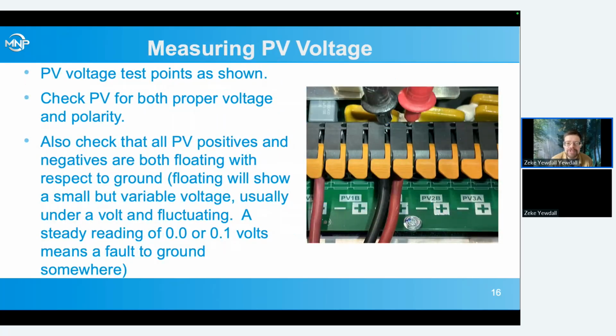Here is a trick on measuring the PV voltage. Those little holes right above the orange flip lever there, that is where you can stick your multimeter test lead to measure the PV voltage coming in. I've heard a lot of people say there's no way to measure the PV voltage with that terminal because there's not a screw on it, but there is a test point on there. So you can stick your test leads in there and verify you've got the correct PV voltage.